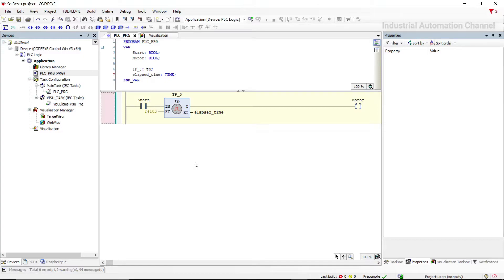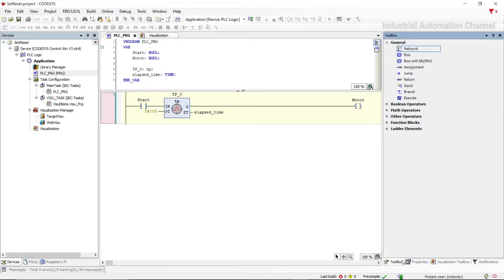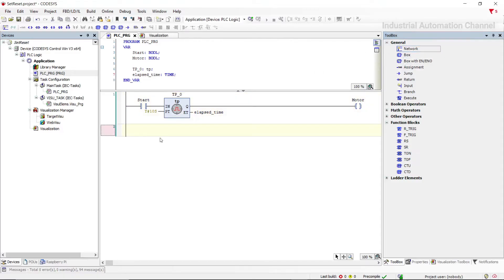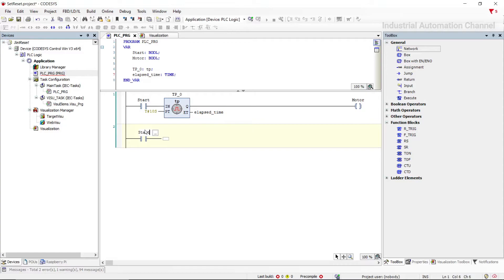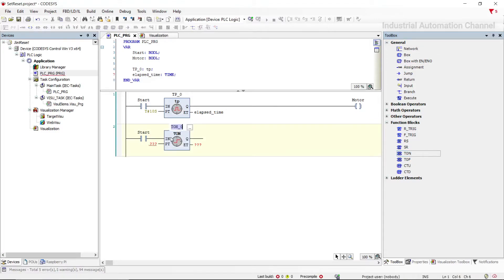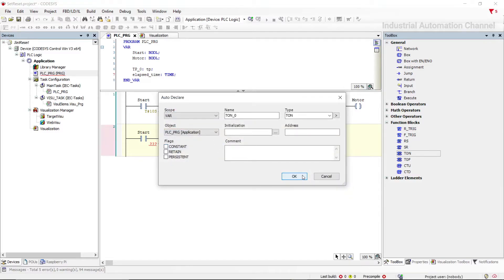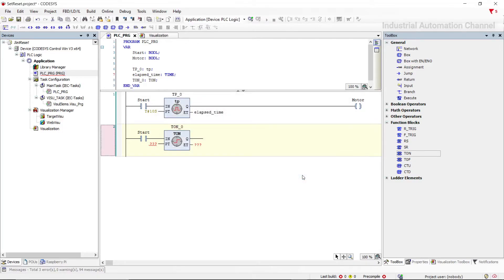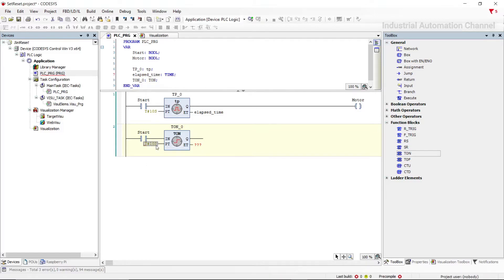The next timer in CODESYS is Timer On Delay, or TON. You can find this timer in function blocks — drag and drop it to insert it into the programming environment. When you press Enter, the declaration window appears and we need to declare a variable of type TON. Like TP, this timer has an input for starting it with type boolean. For the preset time I define it as 10 seconds, and there is also an elapsed time variable with data type time.